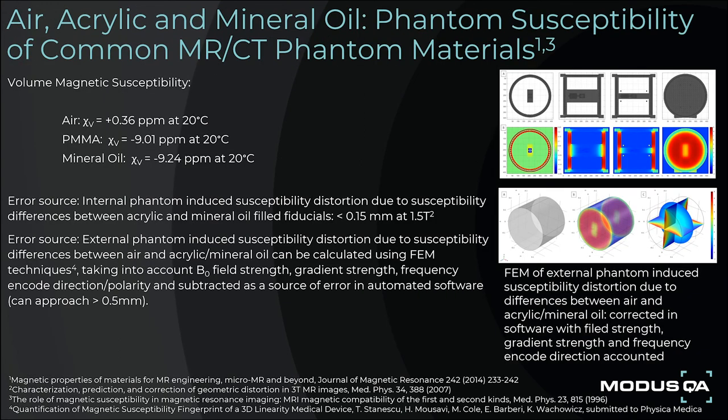Phantom susceptibility-induced distortion is identified as a source of measurement error. The difference in volume magnetic susceptibility between acrylic and mineral oil-filled fiducials has been previously shown to add an estimated phantom-induced distortion of less than 0.15 mm in the frequency encode direction at 1.5 T. The external phantom-induced susceptibility distortion due to susceptibility differences between air and acrylic and mineral oil can be calculated using finite element modeling techniques, taking into account B0 field strength, gradient strength, frequency encode direction, and polarity, and subtracted as a source of error in automated software.